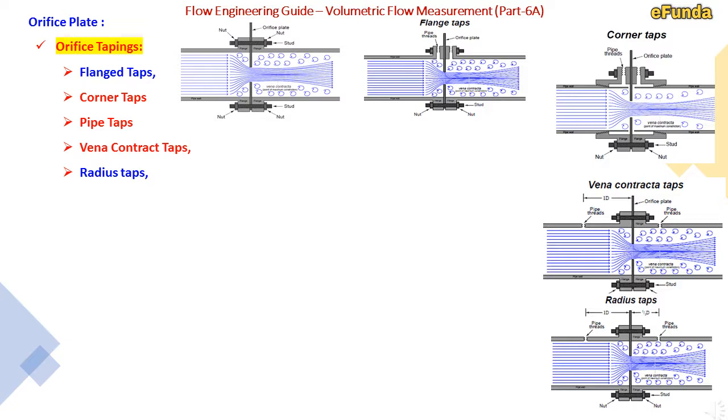Now there are various critical points as well. Minimum flange rating required is 300, to hold the half inch tapping on the flange. To accommodate this half inch tapping for measurement, a minimum flange rating of 300 is required.